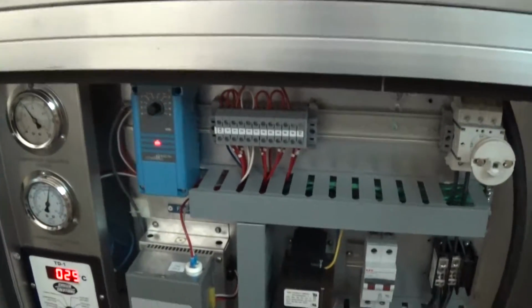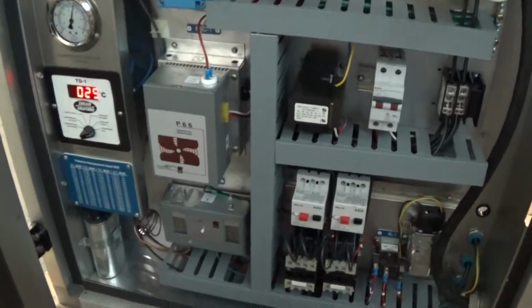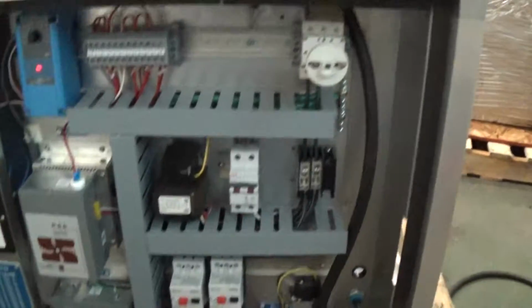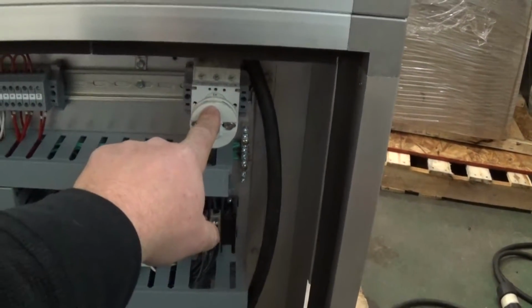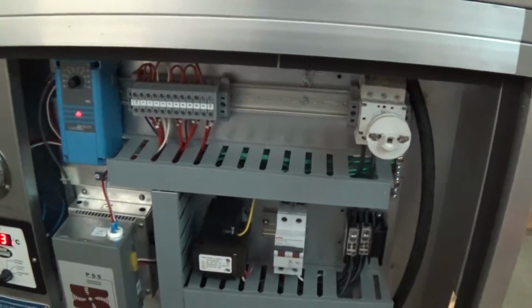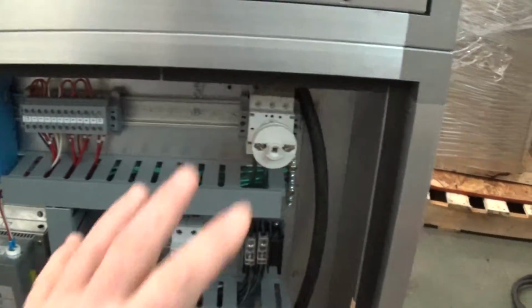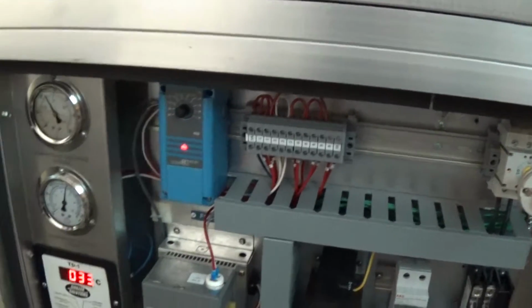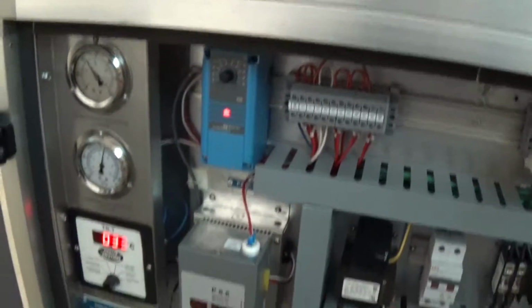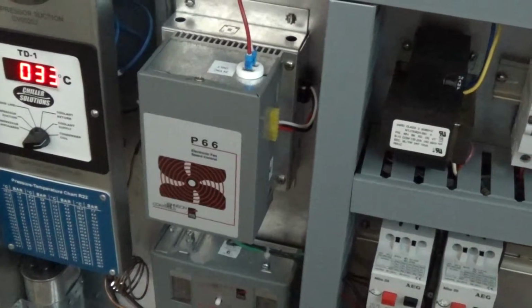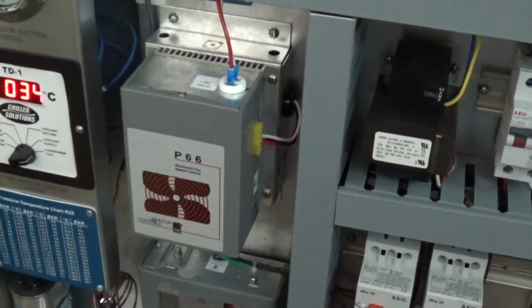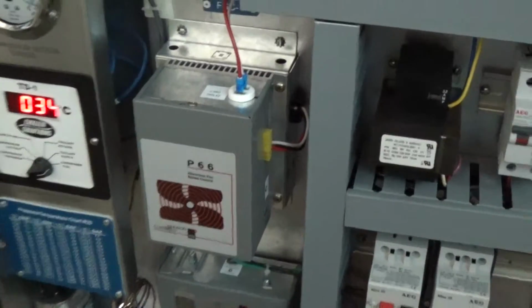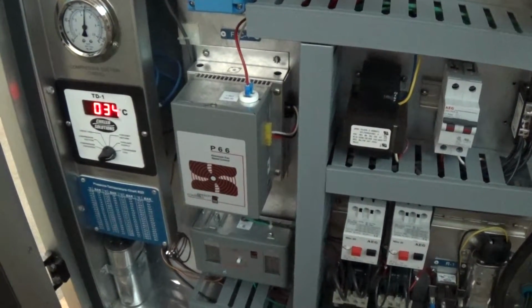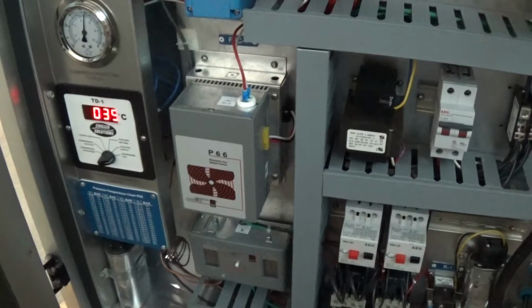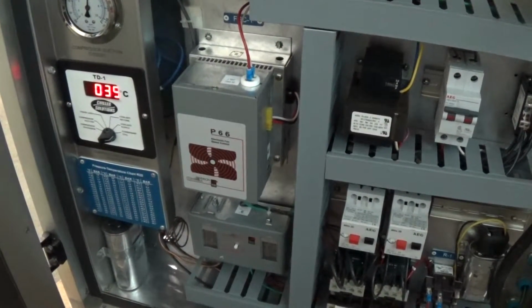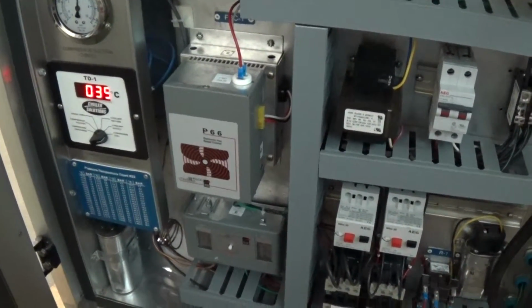So we can hear some noises. The compressor started and the fan started. And before we go look at some of those things, I just want to talk about a couple things in here. That's your main disconnect. We manually turned that on so we could have the cabinet door open. You shouldn't have the cabinet door open and power on the unit. Again, the temperature controller. This here is the low ambient P66 fan speed control. That's so you can run this in colder climates or colder ambient environments. This one's probably going to go indoors, which is fine, but it's nice to know you have that feature.